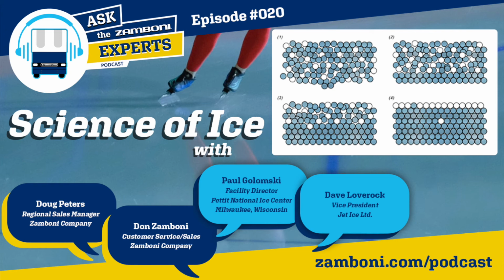You see guys come up with a CO2 extinguisher, and CO2 is heavier than air. So what you really want to do is enclose that area like a box with no top or bottom to it. Slowly squeeze the CO2 into that box and let the CO2 hang in the air and freeze it down. It gives you a patch, but that's all it does. And normally when you finish that patch using CO2, it's good to hit it with a splash of water to bring the temperature back up.